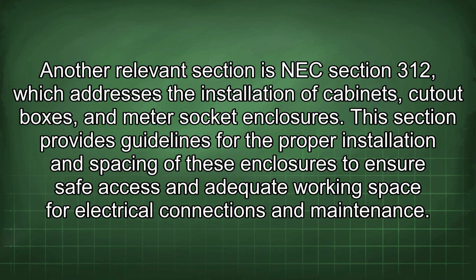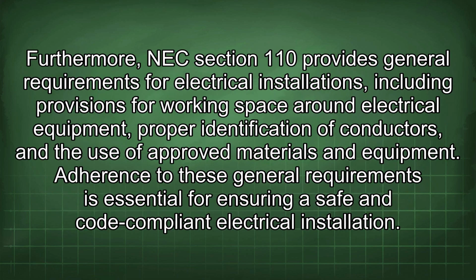Another relevant section is NEC Section 312, which addresses the installation of cabinets, cutout boxes, and meter socket enclosures. This section provides guidelines for the proper installation and spacing of these enclosures to ensure safe access and adequate working space for electrical connections and maintenance. Furthermore, NEC Section 110 provides general requirements for electrical installations, including provisions for working space around electrical equipment, proper identification of conductors, and the use of approved materials and equipment. Adherence to these general requirements is essential for ensuring a safe and code-compliant electrical installation.